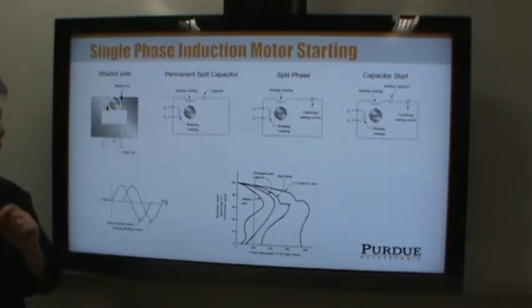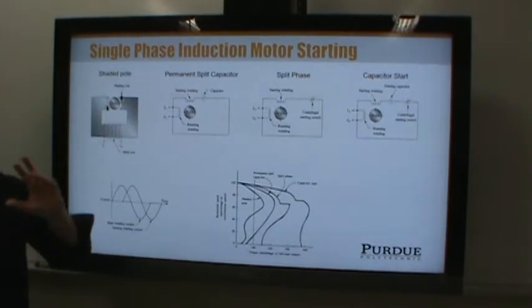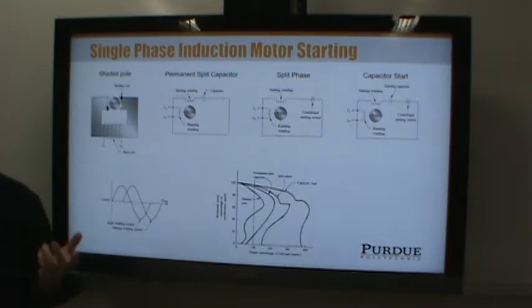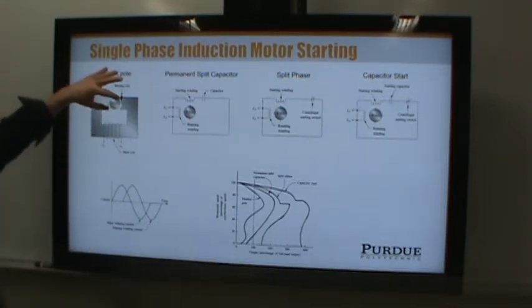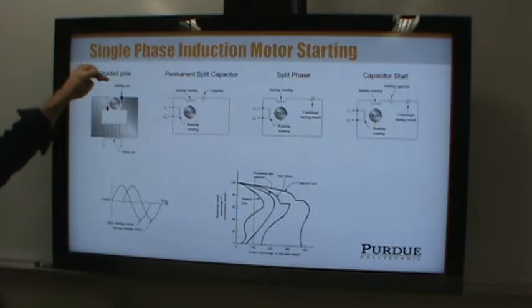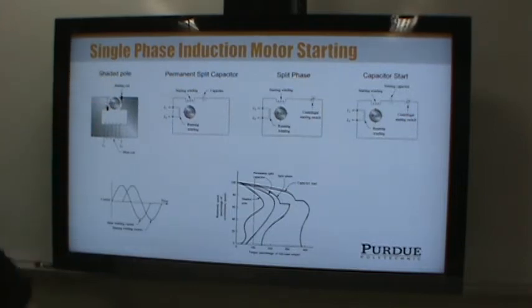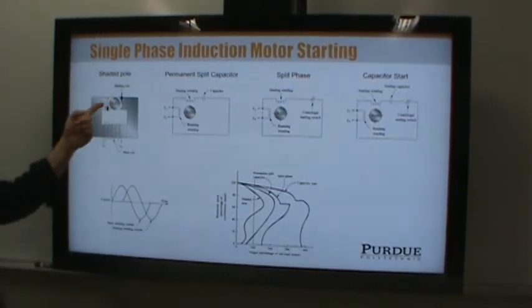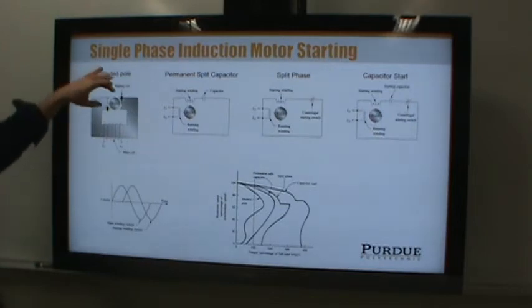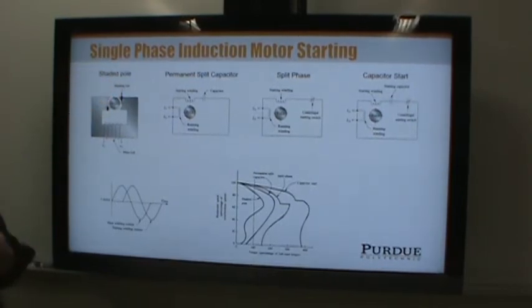When you have single-phase current, you basically can't get the motor to start on its own — it needs some help. By including these shaded poles, it changes the magnetic field so that you can get the rotor to start. What that means is that these shading coils end up sort of dragging the rotor once it's going.